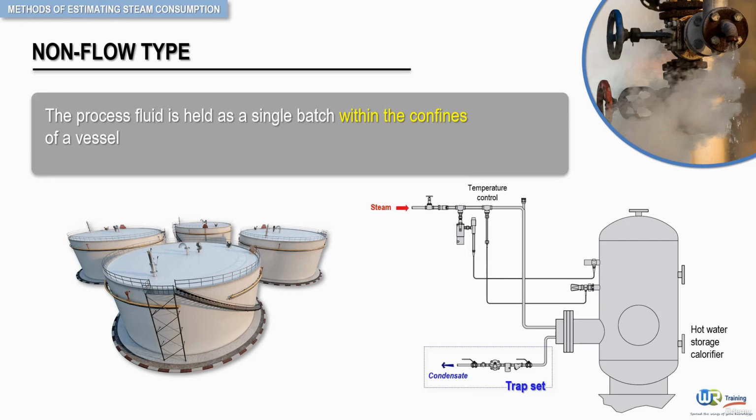In some non-flow type applications, the process heat-up time is unimportant and ignored. However, in others, like oil refinery tanks, it may not only be important, but crucial to the overall process. Consider two non-flow heating processes requiring the same amount of heat energy, but different lengths of time to heat up. The heat transfer rates would differ, while the amounts of total heat transferred would be the same.